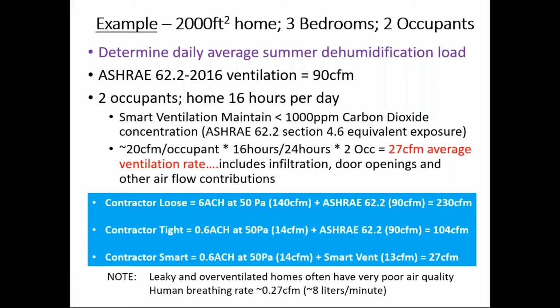Now, we're just calculating the average ventilation rate, but the reality with a smart ventilation unit is that it would be a much higher airflow, in our case about 200 CFM delivered when people are there and where they need it in the home. But this 27 CFM sounds very low as an average flow rate when this table's telling you 90 CFM, and then layered on top of it is the infiltration.